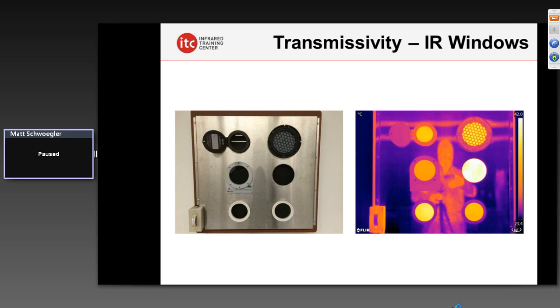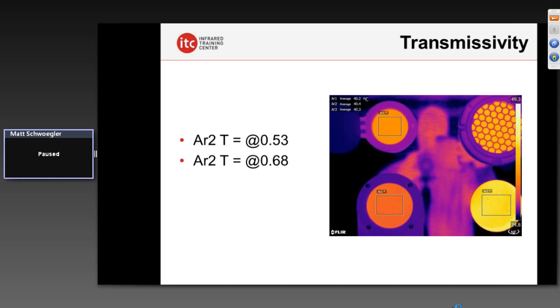Infrared windows provide a safe alternative to having to remove covers. FLIR makes infrared windows — it's a great way to qualitatively evaluate problems through closed panels. But you have to understand the physics behind how infrared windows work — they're not 100% transmissive, which is something else we cover in our training classes. In this lab with various infrared windows set up on the panel, the measured transmissivity of two of these windows is about 50 to 70%. The lower right example is actually an empty hole — that is the true temperature of that surface. The windows are not allowing 100% of that radiation to transfer through, so the surface behind them actually looks cooler.